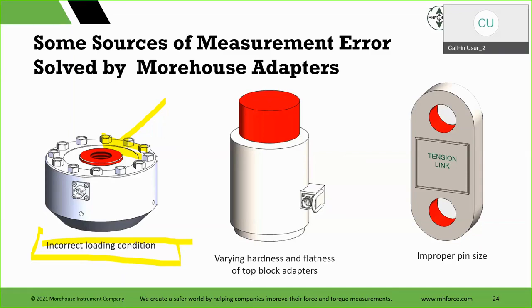Then we have varying hardness and flatness of top adapters. This top adapter, I've seen errors of, you know, 0.3, 0.5. It's just when you buy the load cell and buy the top adapter with it, it is a system. So you're not going to see any of those errors from different hardness. It's going to wear. As it wears over time, it might get a little harder, but it's going to wear with the load cell. You're fine.